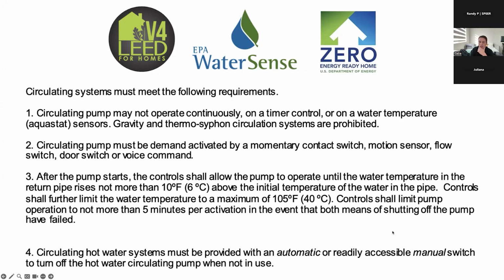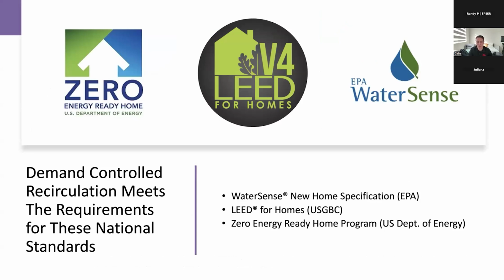Another component of these energy codes says that the pump control shall limit the operation to no more than 5 minutes per activation. So in the event that you turn the pump on and it runs for 5 minutes and the return line is not sensing that temperature rise, then the pump is going to automatically turn off. And why do we do that? Because a very common issue with hot water recirculation systems is you get air trapped in the line. And then when that happens, the pump impeller is spinning, but it's not actually moving water. These pumps need to have water going through them, otherwise they will basically burn out. So this automatic 5 minute timed lockout is a fail-safe to protect the pump from pump cavitation.